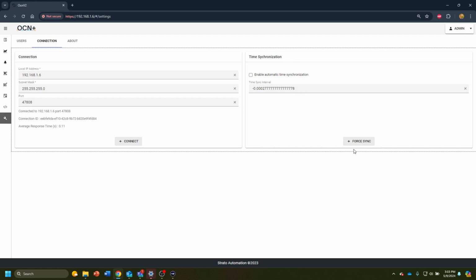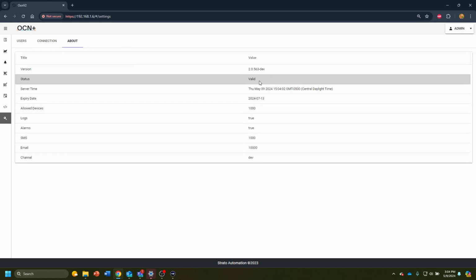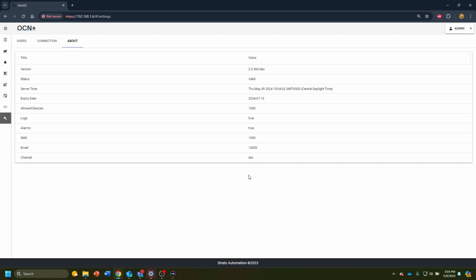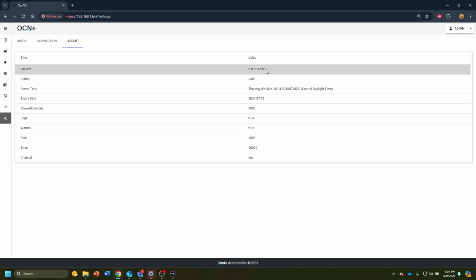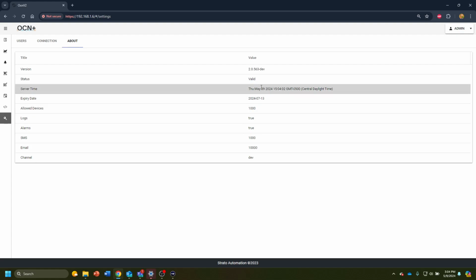So my BACnet IP to MSTP routers connect to my Strato devices. I'll hit connect, and it gives me this information along with a connection ID. Over here you'll see time sync, so I can force a time sync with all the devices I've pulled in. Finally, in the settings tab, I have information about my OCN+ server, like the version I'm currently running as well as some other information about my license.